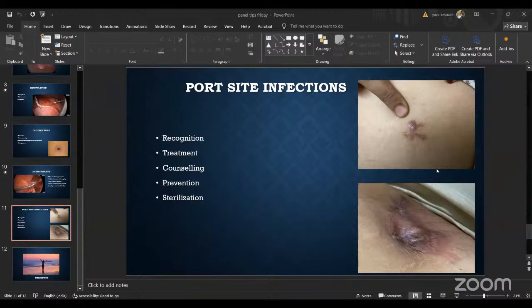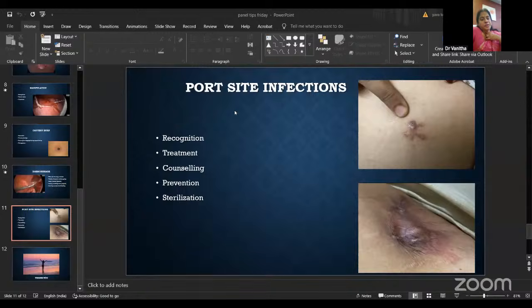Very, very important, there's no replacement for proper sterilization of instruments. People just put it into Cidex and take it out in the second minute. Cidex is only a high level disinfectant, it's not sterilization. Soak it properly for 20 minutes, and before soaking it, the process of cleansing starts from the table itself. Once it's out of the abdomen, the blood needs to be wiped, and then you need to put it in an enzyme solution, wipe away all the blood clots, and if you have an ultrasonic oscillator, it's better to put it in that.